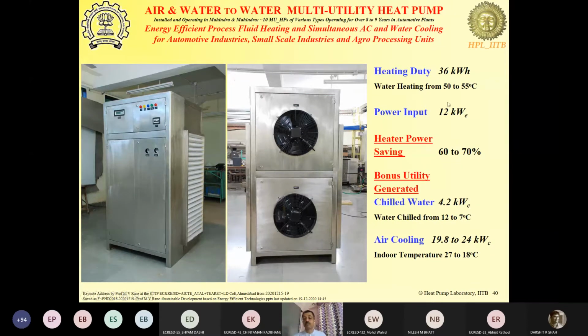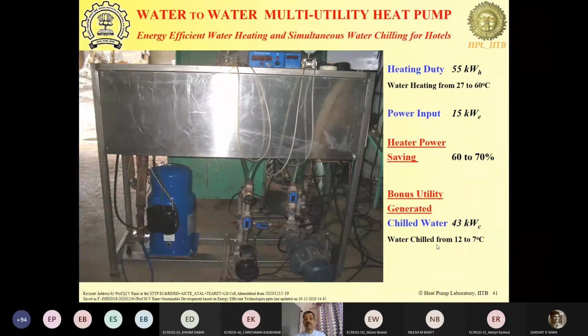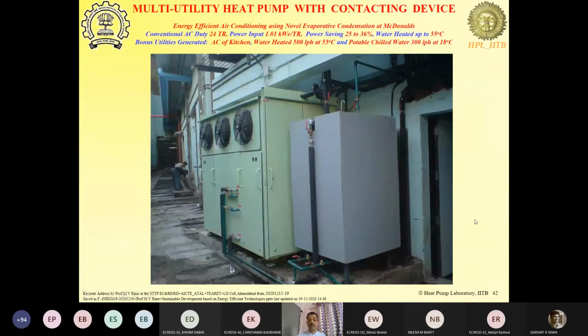Okay. So this was with 12 kilowatt input, we are giving 36 kilowatt of heating, and we are simultaneously giving up to 24 kilowatt of air conditioning. And if part of the air conditioning is tapped out as chilled water, then you get reduced air conditioning. Then we also had a water-to-water heat pump for textile application, where water was heated from 27 degrees to 60 degrees centigrade. 55 kilowatt of hot water was produced with only 15 kilowatt of input electricity, and 43 kilowatt of chilled water was co-produced with that. So this can be used for air conditioning, and this can be used as a hot utility. So overall COP, if you look at it, is very high.